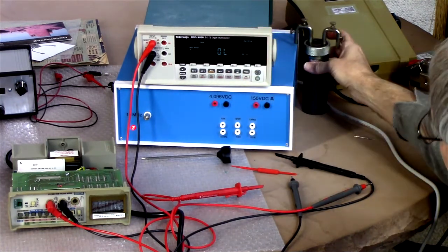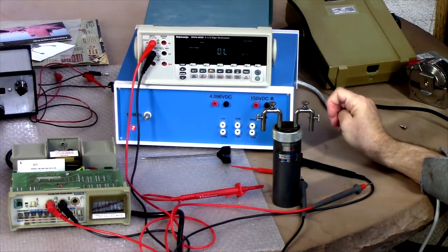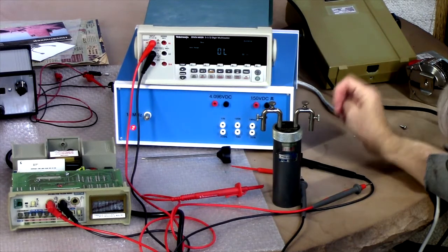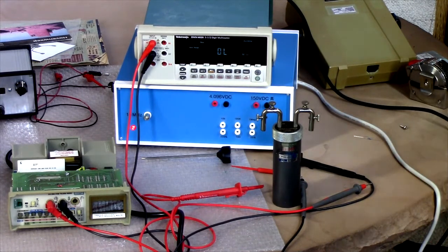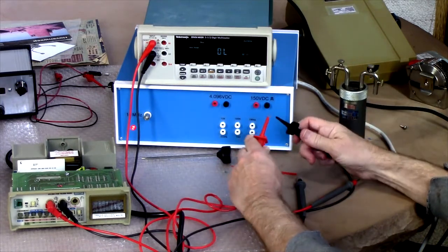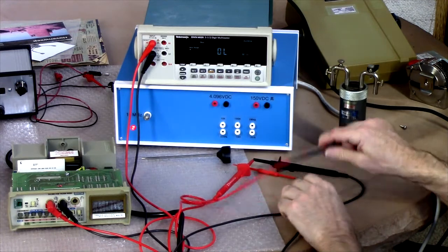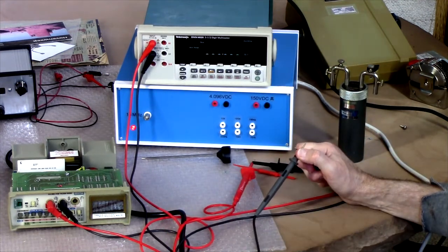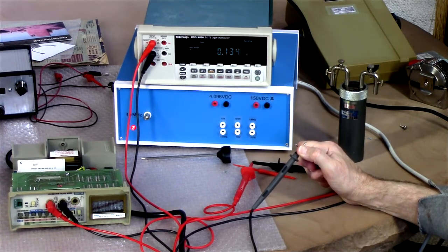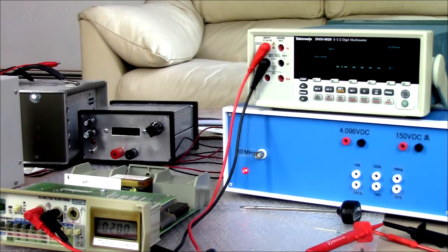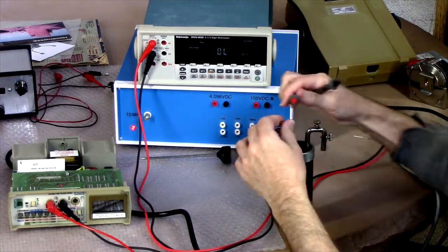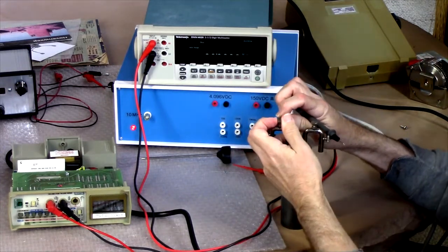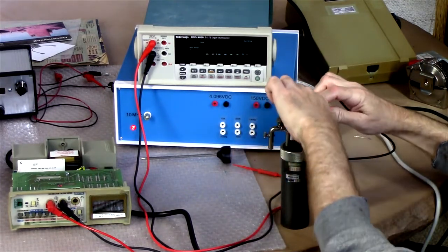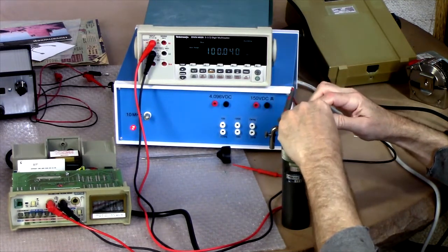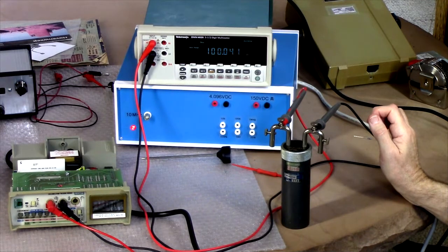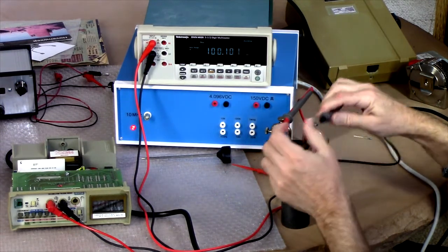And for that, let's start with the 10 ohm. Well, no, because it has resistance test. Okay, first of all, short the leads together, right? There is one adjustment on resistance, and that's on the 200 ohm range. I see about 0.2 in both leads. Okay. This is the Tektronix. This is 100 ohms. And no, I'm not going to do 4-wire. Okay, 100.04.